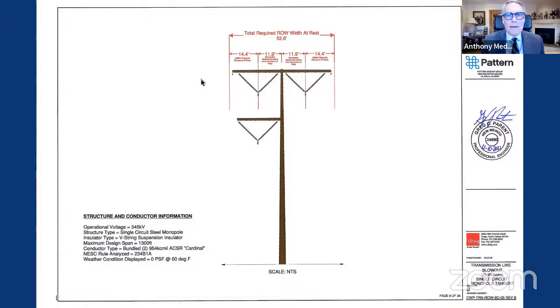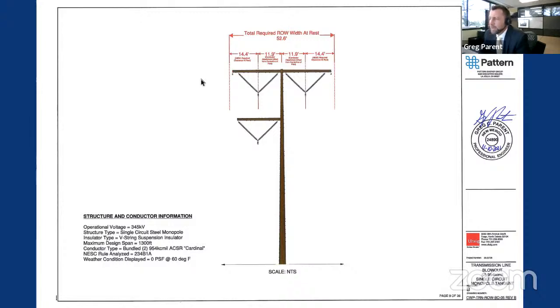Rough rule of thumb is that the minimum right-of-way width for 345 kV lines is 150 feet, and a maximum span would be around 1,700 to 1,800 feet. Does that sound about right? That seems like a big span. Yeah, you would need very specialized structures to achieve something that big. There could be canyon crossings and things like that would require it, but I would definitely not say that's a typical span length.